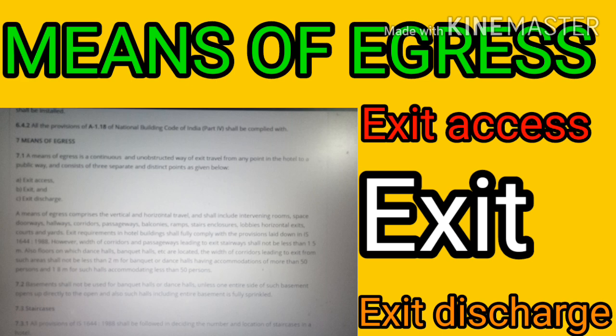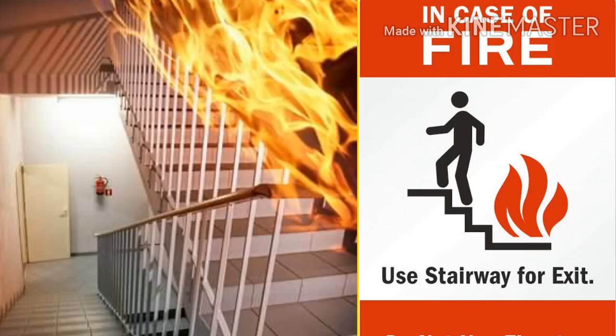Exit requirements in hotel buildings shall fully comply with the provisions laid down in Indian Standard 1644-1988 rules and regulations. However, the width of the corridors and passageways leading to exit staircases shall not be less than 1.5 meters. Also, on floors on which dance halls and banquet halls are located, the width of the corridor leading to exit from such areas shall not be less than 2 meters for banquet or dance halls having accommodation for more than 50 persons and 1.8 meters for such halls accommodating fewer than 50 persons. It's a very important thing. Basements shall not be used for banquet halls or dance halls unless one entire side of such basement opens directly to the open, and also such halls including the entire basement are fully sprinklered.